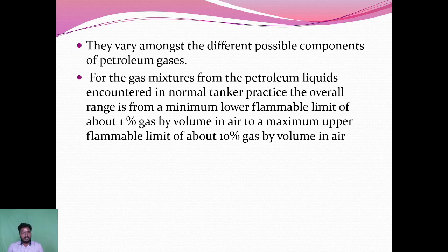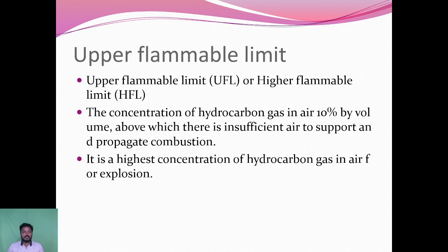They vary depending on the different possible components of the petroleum gases. For the gas mixtures from petroleum liquids encountered in normal tanker practice, the overall range has a minimum lower flammability limit of about 1% gas by volume in air, and a maximum upper flammability limit of about 10% gas by volume in air.